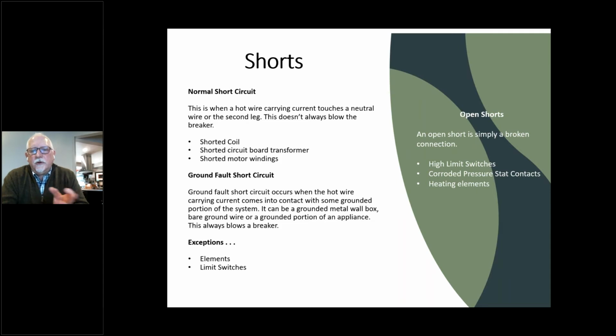So on shorts, you've got normal shorts, and you've got ground fault shorts, and then what Don Berquist refers to as open shorts. A normal short circuit happens when any of the power lines makes contact either with another power line or with a neutral, or not particularly with ground. For example, you can have a shorted coil where the coils are shorted together, and the coil no longer functions, but it's getting resistance, but it hasn't blown the circuit, because that resistance forms a little heating element and it gets warm. It doesn't work, and it is a short circuit, but it's not evident because the circuit breaker isn't blown. You could have a shorted circuit on a board transformer, so the circuit board doesn't work anymore, but everything else gets powered, everything else is fine.